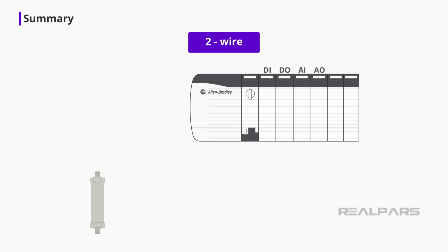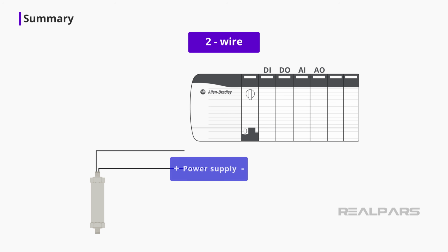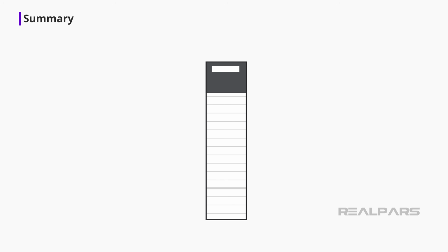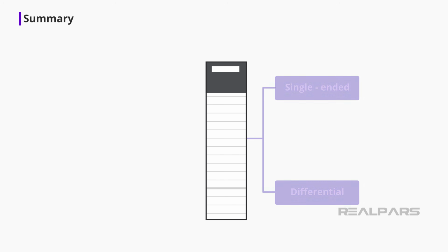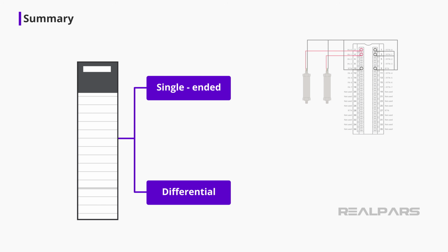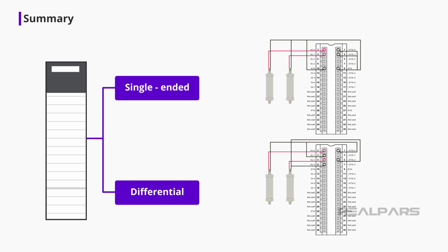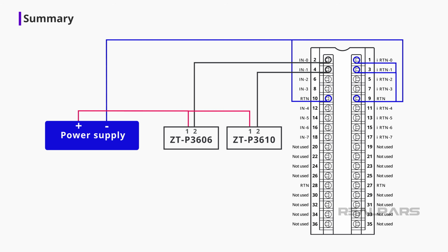Most pressure transmitters are two-wire types, having two wires that provide power for the transmitter and are also the signal lines. PLC analog input modules can be wired in two possible modes, single-ended or differential. The selection is important, as it determines how the module is physically wired. In single-ended mode, two-wire transmitters can share a single power supply. That should do it for this video.